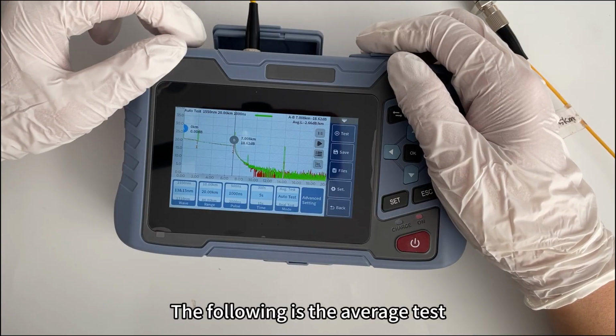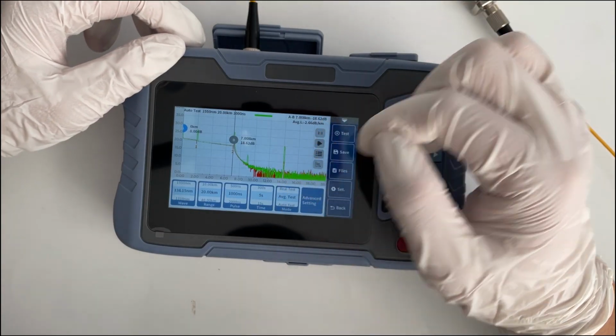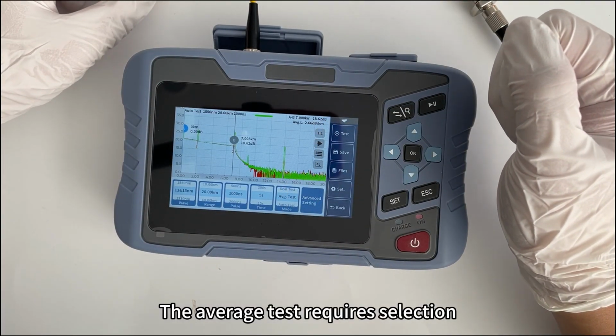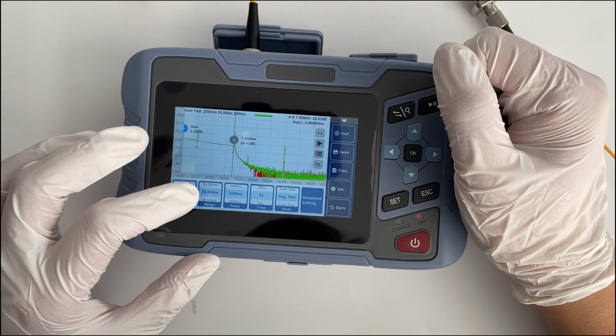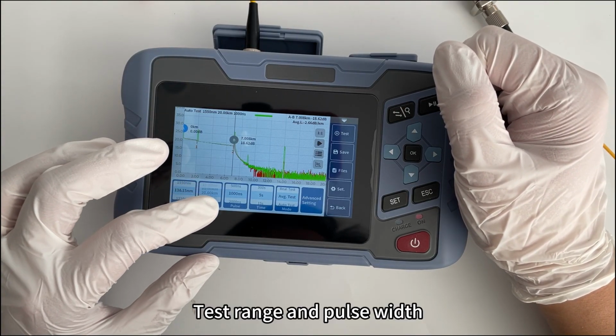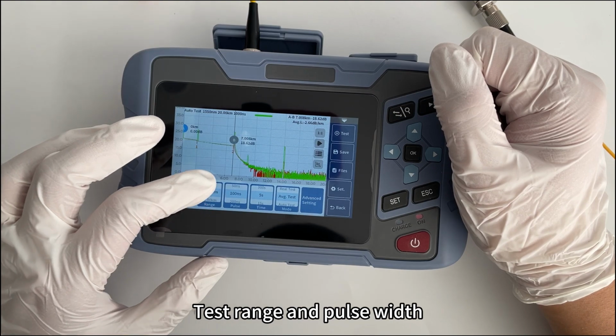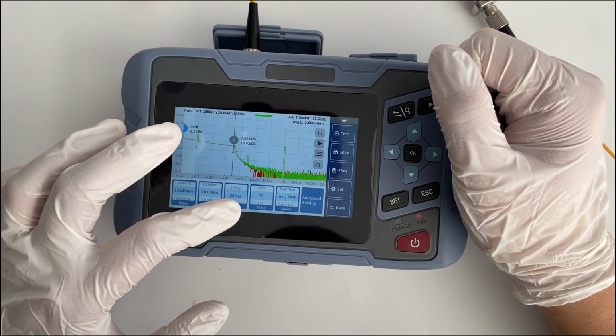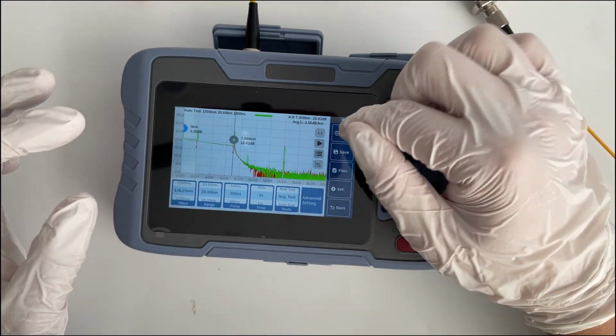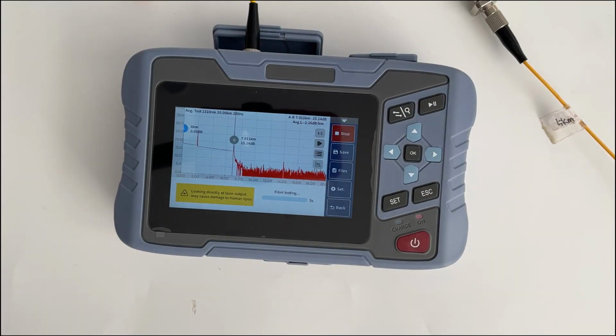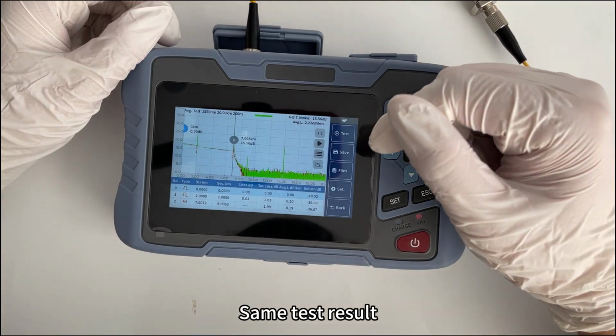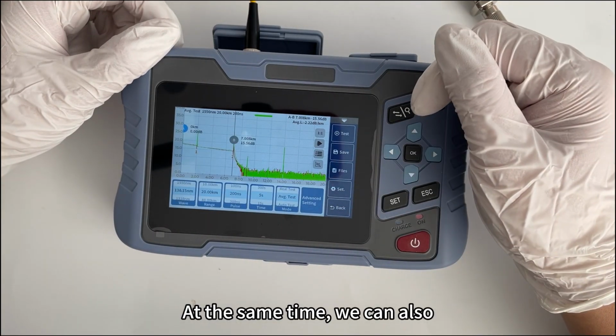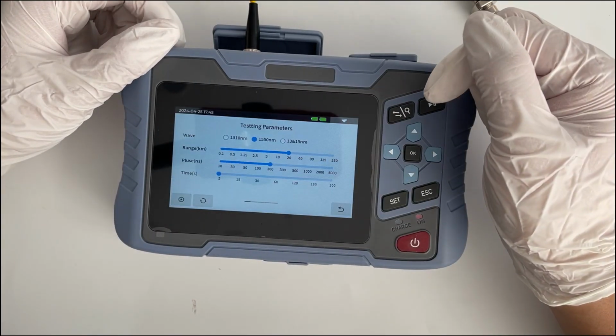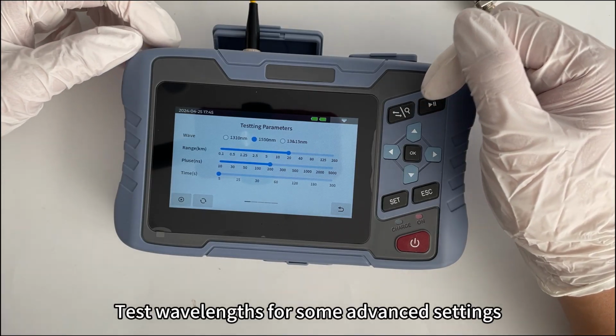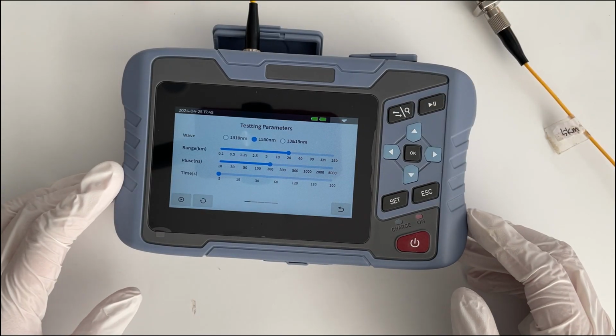The following is the average test. The average test requires selection of the test range and pulse width. Click Test. Same test results. At the same time, we can also test wavelengths for some advanced settings.